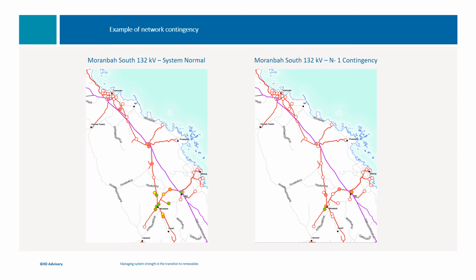The diagram on the right shows what happens under worst case N-1 contingency, and you can see there that a single 400 MVA unit really doesn't provide system strength over a significant part of the network. And in that case, a better approach will be to provide multiple, say up to 4 medium-sized units to overcome those N-1 contingencies.